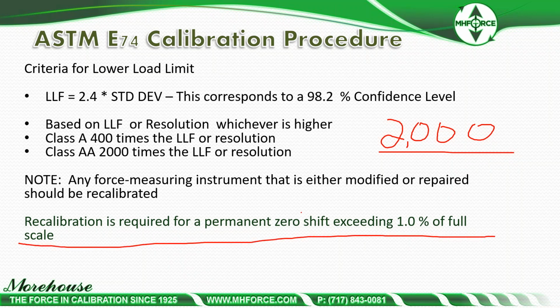This is per the standard. So the customer has a device, they overload it. They're not sure how much they overload it. The load cell still works. They think everything's good. They send it in for cal, and then we see this large shift in the data. That large shift in the data can put them way out of calibration, but this is the whole reason: if you think you've overloaded a cell and you have a shift by more than 1% of full scale, it needs to be recalibrated.